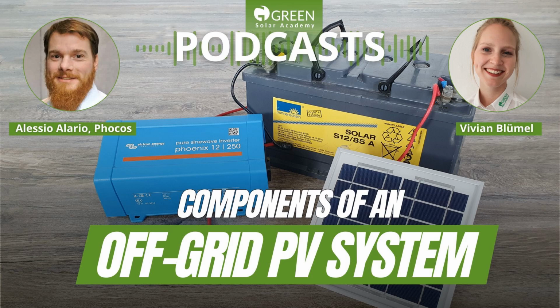What about lithium batteries? Lithium batteries are easier in some respects and more complex in others. Easier in that they're actually simpler to charge. There tend to be only 2 stages, maximum 3 charging stages, whereas for lead you tend to have 3 to 5 stages, depending on the different products and manufacturers.